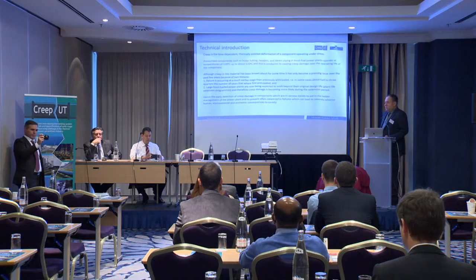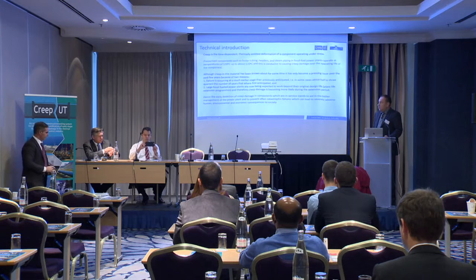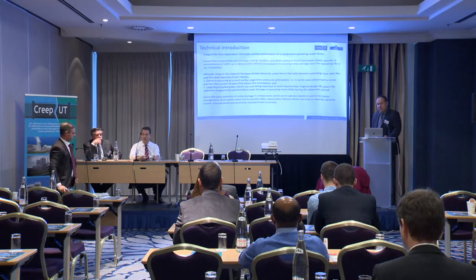Short technical introduction: creep is a sort of damage that happens in power plants, in pipes working under high temperatures and high mechanical pressures. Typical temperatures in such plants are above 540-550 degrees, and with the mechanical pressure and such high temperatures, the steel suffers deformations that have different phases. If kept long enough under such pressure and temperature, the pipes can actually crack, causing very large financial, security, and safety problems.